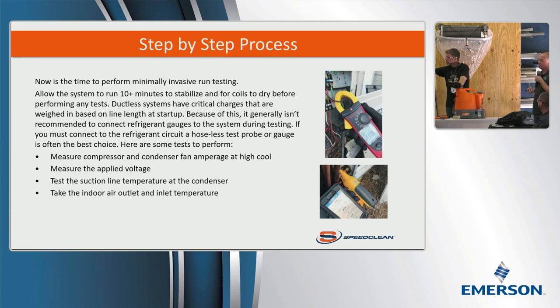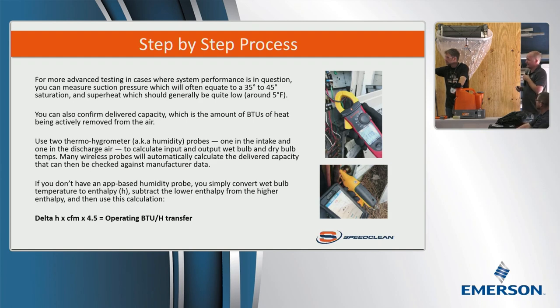I say measure the applied voltage because that's the sort of thing you're supposed to do, supposed to say. But it's not nearly as critical as checking your discharge outlet air temperature. I want to get to this slide, and it's in the guide, which explains how to do the underload test, the actual delivered capacity, running under normal conditions to see if it's producing proper BTUs. This gives you the calculation: delta H times CFM times 4.5 equals operating BTU transfer.